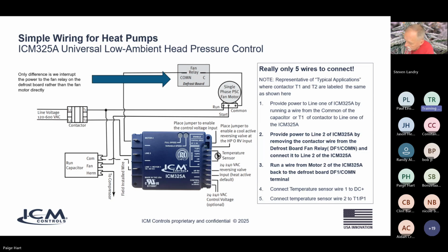So that's paralleling 24 volts off of the defrost board to that HPRV input. It's either going to be 24 or 240 if it's a line voltage reversing valve. You're just paralleling that voltage off of your defrost board, and then you're choosing which direction you need to go. If you have a cool active reversing valve, you have to place a jumper at HPORV. If it's a heat active reversing valve, you need no jumper there. Control voltage on this control is optional, so you don't need to wire that in.